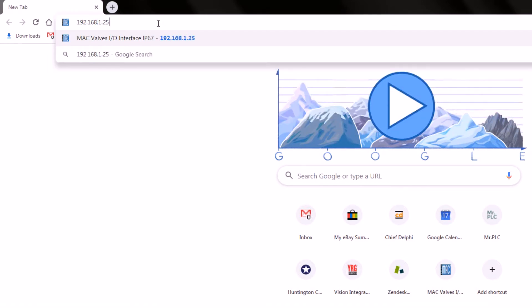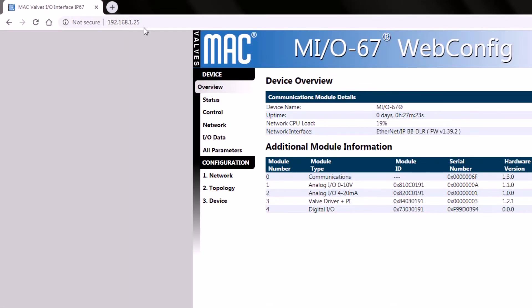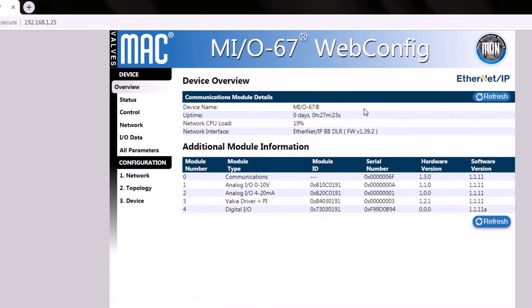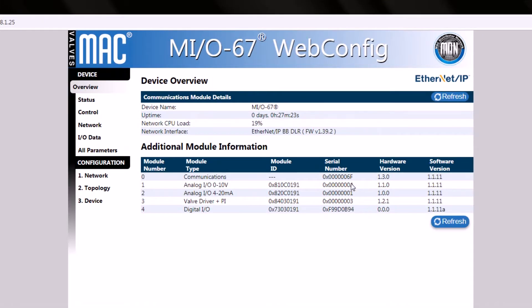Our default IP address is 192.168.1.25. This brings up the MIO67 web config utility that we can use to determine what the comm module believes the modules attached to the left are. Here we can see a summary of the modules. In slot number one, we have an analog I/O 0 to 10 volt voltage analog I/O module.